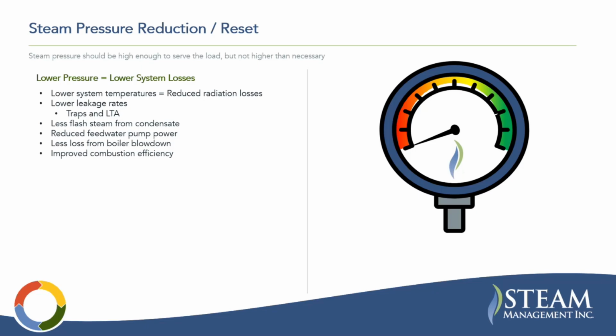You're going to reduce your feed water pump power in the case of high side pressure reduction, where you're reducing your pressure in the boilers. Now those feed water pumps have less pressure to pump against, and there's an electrical savings there. Reduced pressure in the boilers also leads to less loss from boiler blowdown, because even if you have the exact same blowdown flow, now that flow has less energy in it, and so that mitigates that loss somewhat.